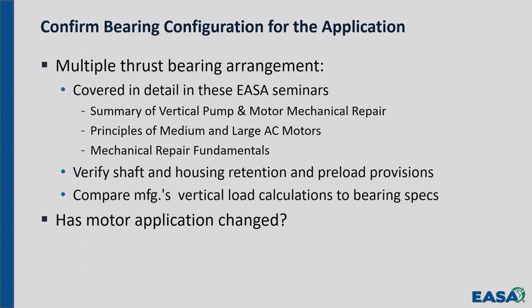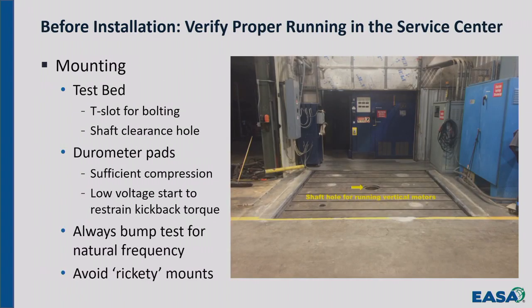All right. You can do a lot to help yourself if you will test run the motor properly in a service center before it goes out. I would guess that most people do that. There are some tests that can be done there that will help when it gets out on the job and there's a problem, particularly for vibration. This is a test bed, and notice it's got a hole provided, so if I have a solid shaft vertical motor, I can bolt that thing down and test run it.